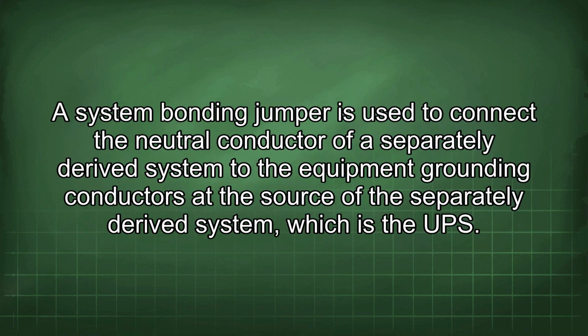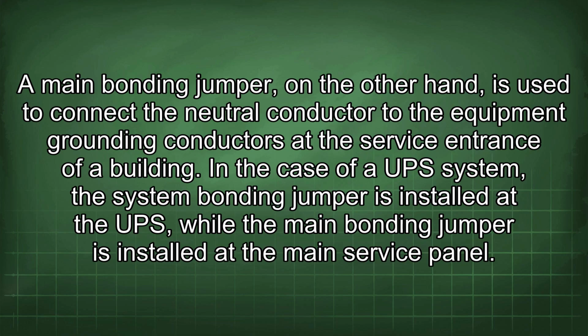jumper. A system bonding jumper is used to connect the neutral conductor of a separately derived system to the equipment grounding conductors at the source of the separately derived system, which is the UPS. A main bonding jumper, on the other hand, is used to connect the neutral conductor to the equipment grounding conductors at the service entrance of a building. In the case of a UPS system, the system bonding jumper is installed at the UPS, while the main bonding jumper is installed at the main service panel.